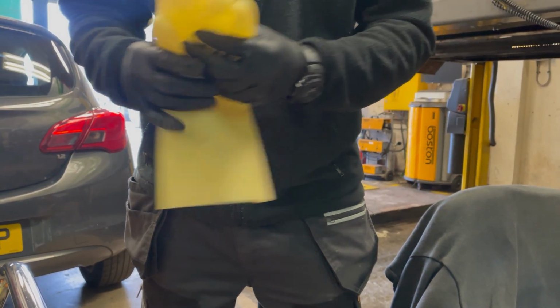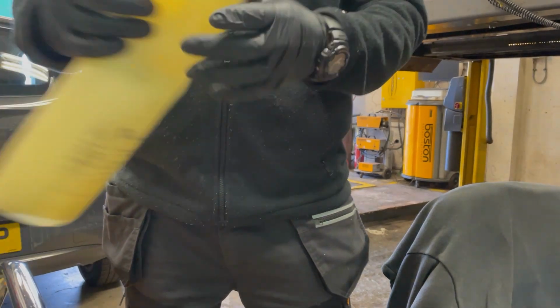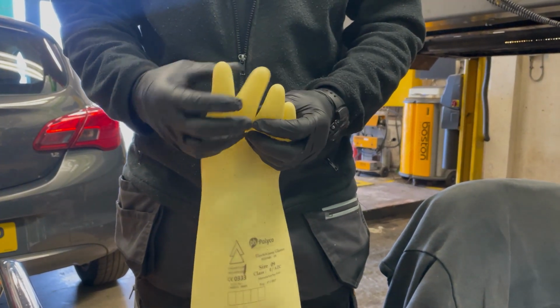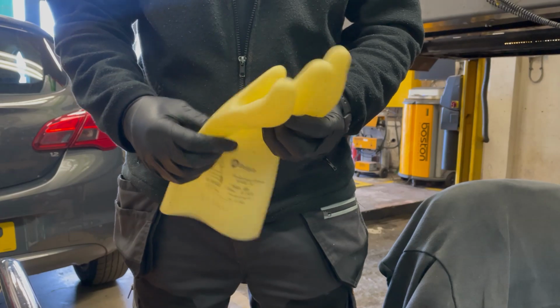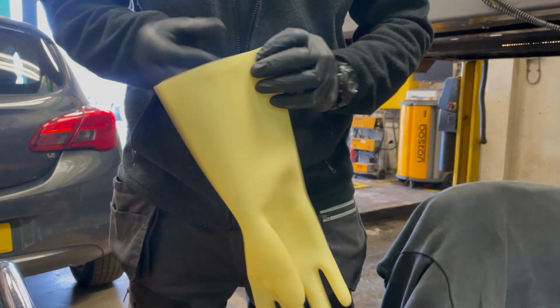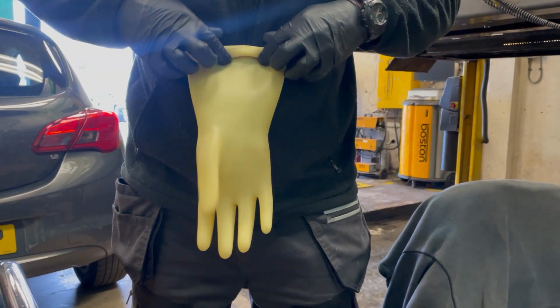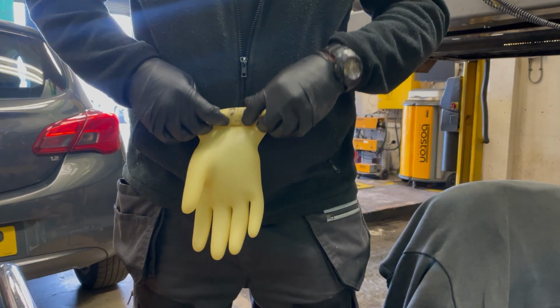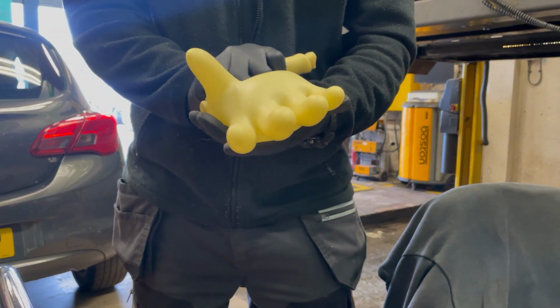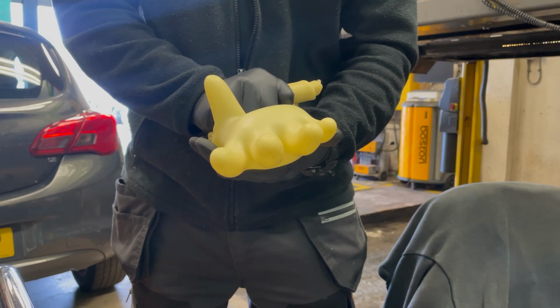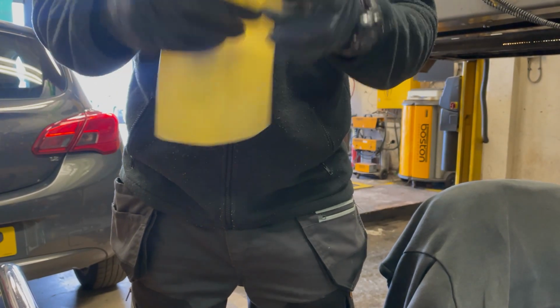So that glove's okay. Second glove, again, these are pretty much brand new, only used once before. They look okay, let's trap the air in them. Always check them every time you do a power down - they've got to be tested every single time you do this procedure. Both gloves are alright, we've checked them, we're happy, we can use them.